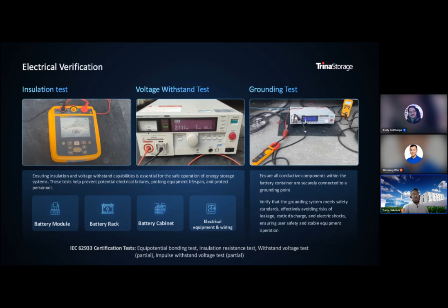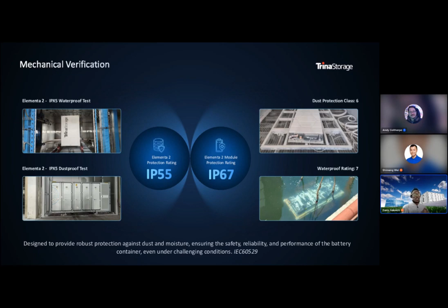That was electrical. Mechanical verification - again, one fault I identified earlier with the previous incident was an electrical issue that got carried over into the battery. I've talked about the mechanical side of things, which is if you don't design an enclosure that's weatherproof - and when I say weatherproof, it can withstand significant adverse weather, and this is what we want. So we don't have a situation where there's a thunderstorm that breaks the enclosure and then there's a leak into the battery that causes a short circuit.